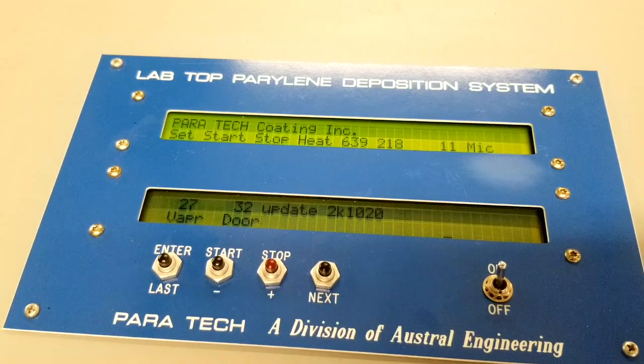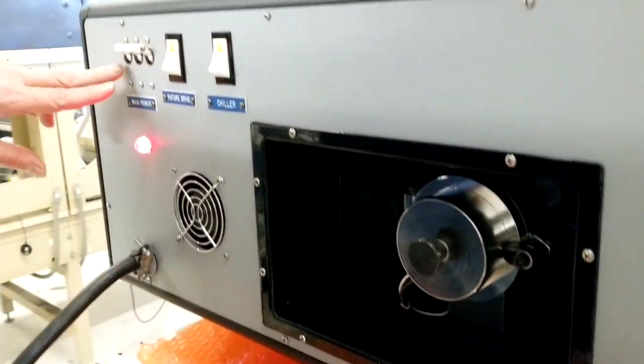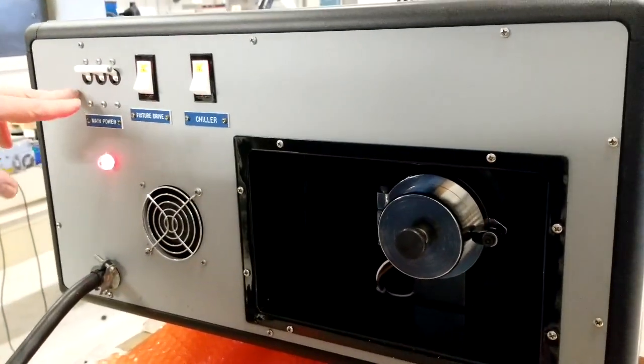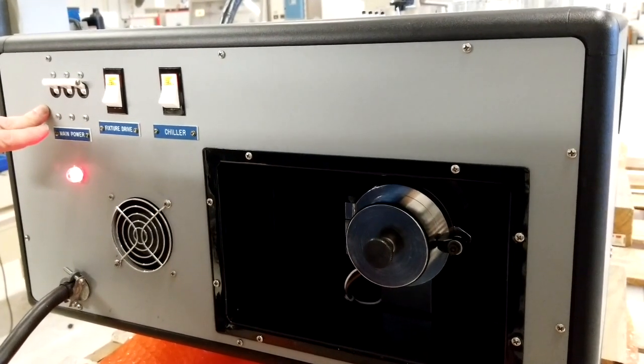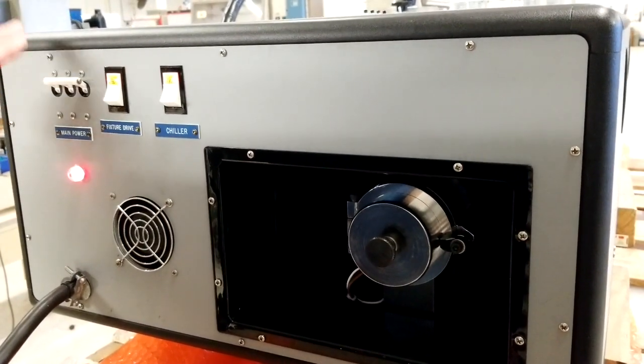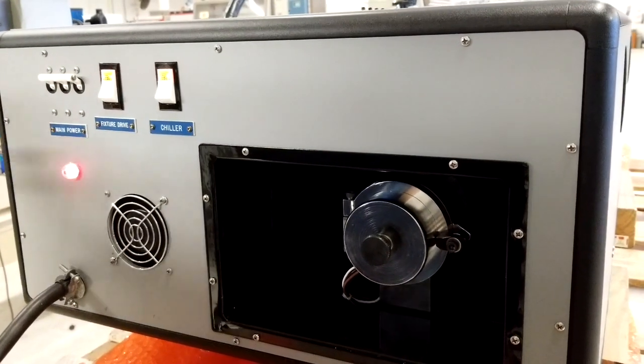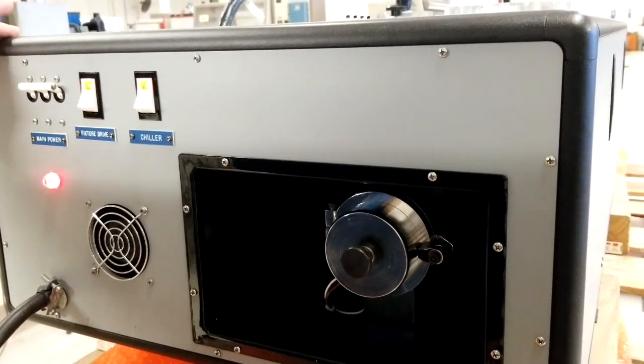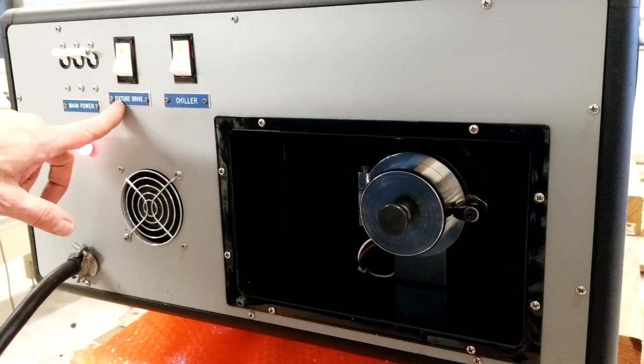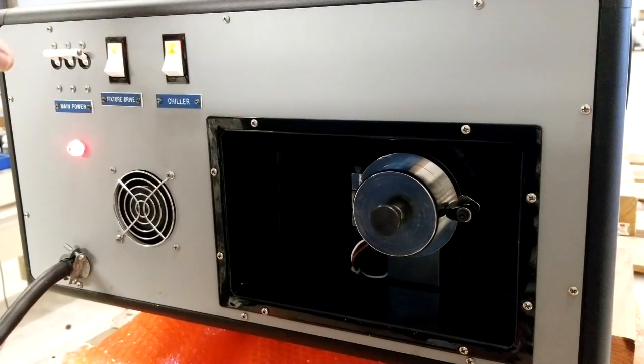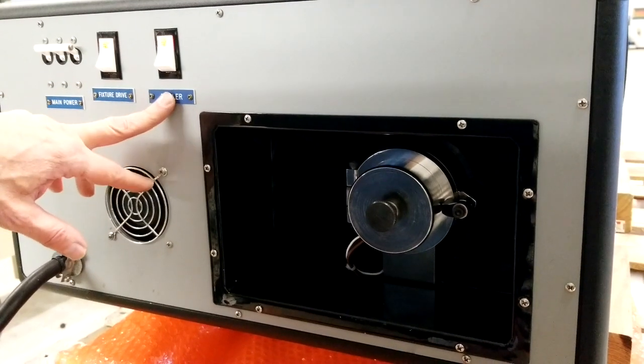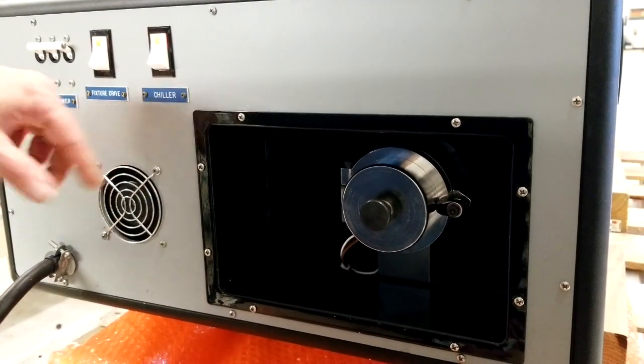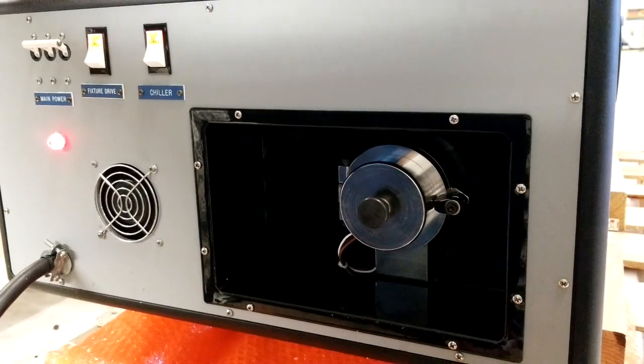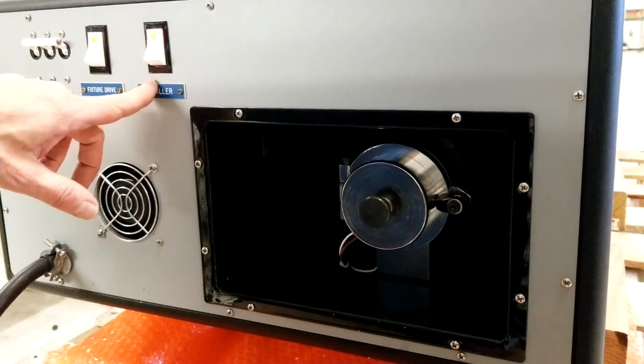And while we're here, you come over to the side here. I just want to point out a few things. This is your main power to the system. The power requirement is 208 single phase with a neutral and a ground, so that requires 4 wires, 2 phases, a neutral and a ground. This turns on your fixture drive. I'll point that out later. It's over on the side. That's where your fixture is loaded in, and then your chiller. Power for your chiller. There's a plug in the back. You may have seen that when we did the walk around. The power for that is here.